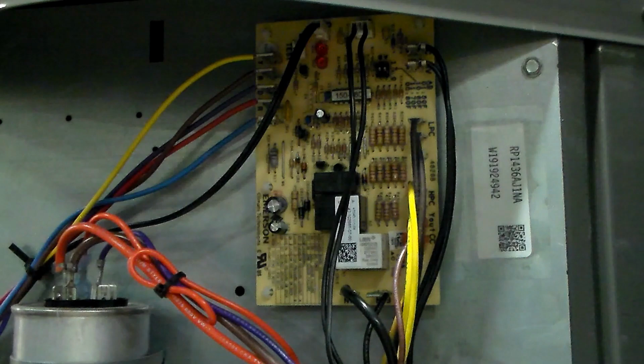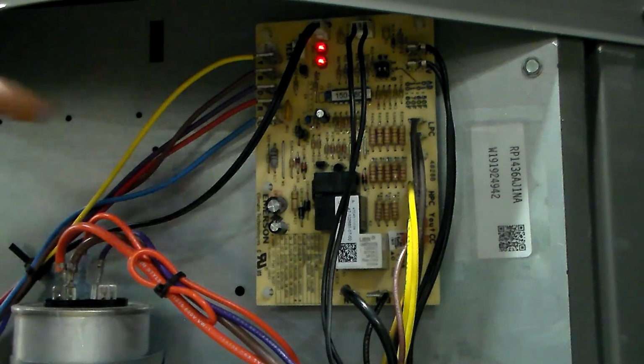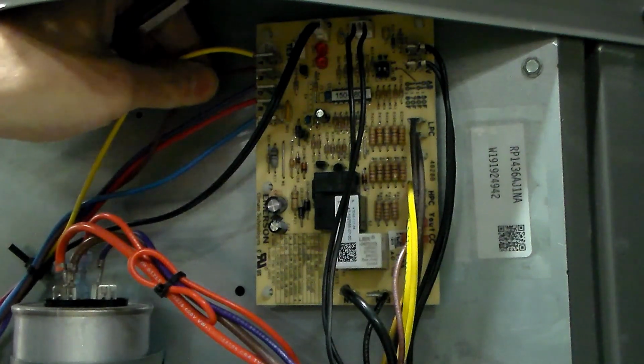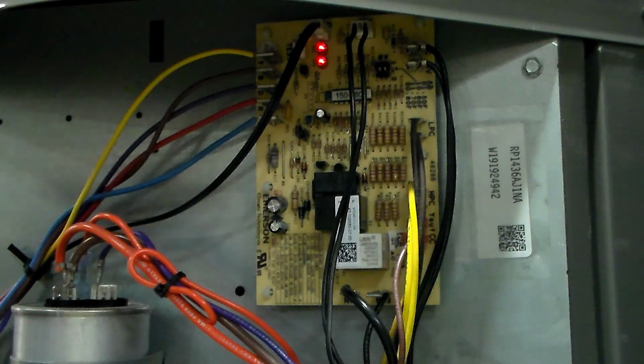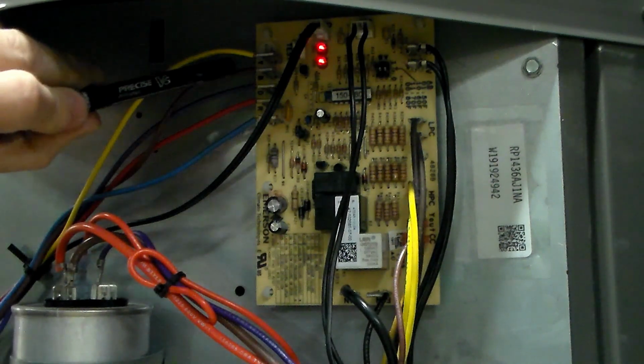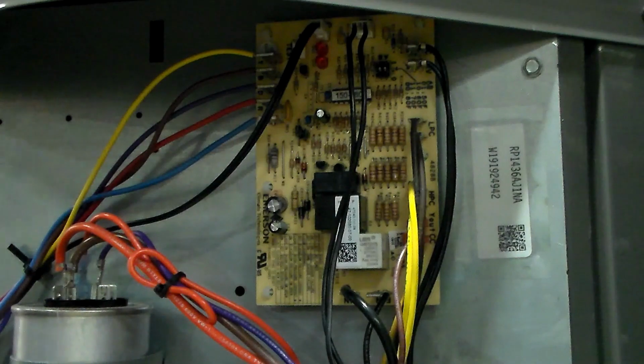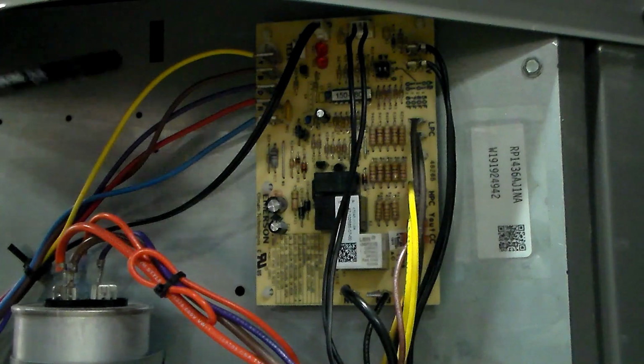Actually there's a legend on the board here for the LED codes, but the panel of the unit tells us what all this stuff means. Then of course we have our Y, and we have B, and then we have D, and R and C. So Rheem, instead of doing O, they do B. On your thermostat, when you program it, you have to set it for O or B, because the thermostat needs to know if it's energizing the reversing valve in heat mode or in cool mode. For Rheem, it fails into cool mode, so it's going to energize the reversing valve in heat mode, which is opposite of what we've been looking at so far. So it's going to be a B terminal instead of an O terminal.